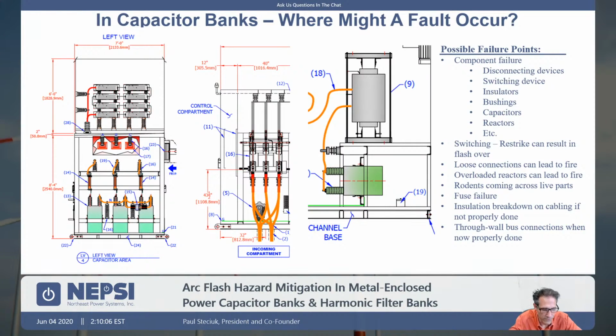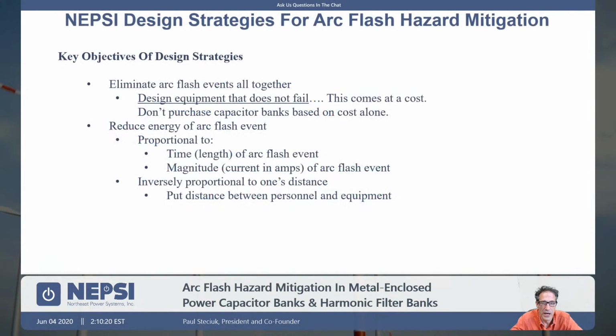So properly specifying the components and properly designing the equipment can lead to a more reliable, safer piece of equipment to operate. Things such as the signage in front of the enclosure and the way it operates the protection and control system all can lead to a safer piece of equipment. So from NEPSI, we see some design strategies to reduce the arc flash hazard. One of those is just to eliminate the arc flash event altogether. Design equipment that does not fail. This comes at a cost.